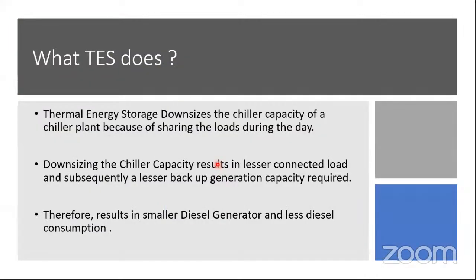So what TES does, the thermal energy storage system downsizes the chiller capacity of the chiller plant because of sharing the load during the day, which further results in the lesser backup generation capacity required, like I just mentioned, and then it results in smaller diesel generators and lesser diesel consumption also.